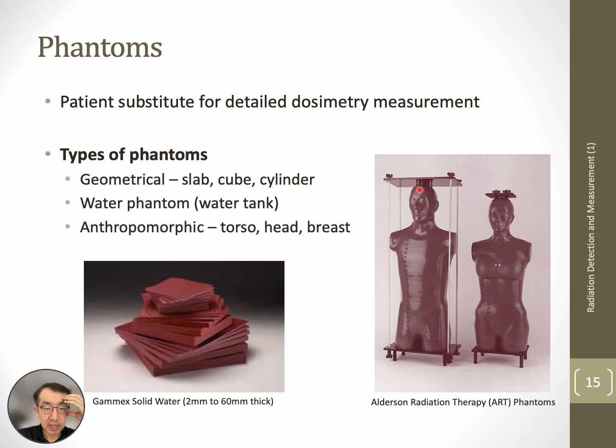It is designed per slab, so you can actually open up and break them up. You can put some film in between the slabs, or some phantoms are designed so that they can have some TLD or OSLD inserts. So you can actually place these detectors inside this phantom, and then you can irradiate as if it is a real patient, and you can assess some dose without risking your patients.